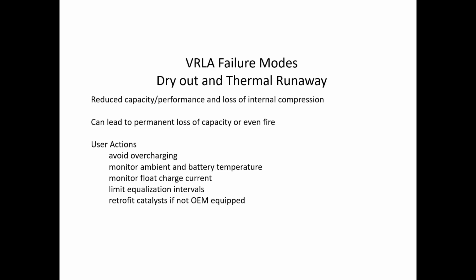Now, the other thing with a high temperature or a high charge current on the battery, you're going to dry out that battery. You mentioned that one-way pressure relief valve will off gas when pressure is built up due to high temperature or high charge current. Once that gas is gone, there's a process to put it back in, but most service people don't do that, and they're honestly not encouraged to do that. So once that gas is gone, you start to lose surface area contact of the glass mat and the plate. The battery is going to start to actually try to draw more current to charge the plate, and it's going to create more heat, and it's going to drive off more gas, and it's called thermal runaway, and it's a condition once the battery starts.